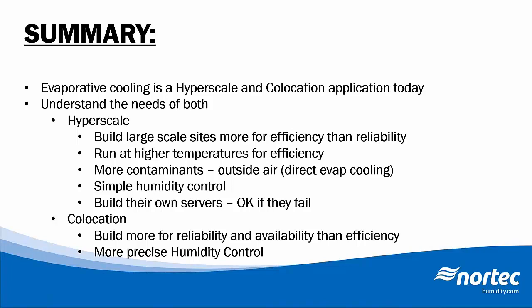And generally speaking, hyperscale is building more for efficiency than reliability, so they're the biggest play for evaporative cooling. Co-location is still building for high reliability, more so than efficiency, but because they're getting so large, they're a little bit of a hybrid where you'll see a little bit of both applied. So hopefully that helps everybody understand some of these terms that are getting thrown around out there, what types of data centers there are, and where this new emerging evaporative cooling technology is going to fit.